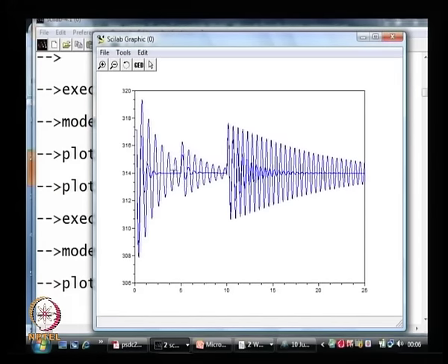Well, you notice something? The original program, the damping was much higher. Whereas now, in all the transients which are considered, one thing you can notice is that the transient takes a longer time to die down. In fact, in a synchronous machine with one damper winding less, it appears that the damping has reduced. This is not very surprising. One may say that the damper winding derives its name in some sense from the damping effect that it has. So, if you reduce the amount of damping, that is by removing one damper, it is not surprising that we get this larger time for decay of the transient. Okay. So, this is something which is not at all surprising.